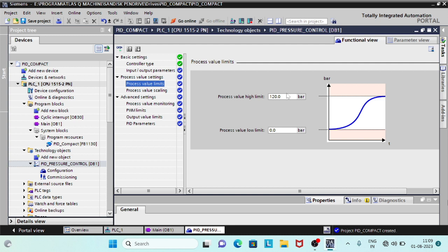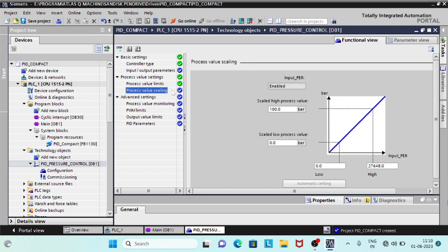Select Output PWM when using a digital output channel. Enter the process value high and low limits. Since we have selected Input PER, we need to scale it inside the PID Compact block. Assume the maximum pressure value at 27,648 is 300 bar.